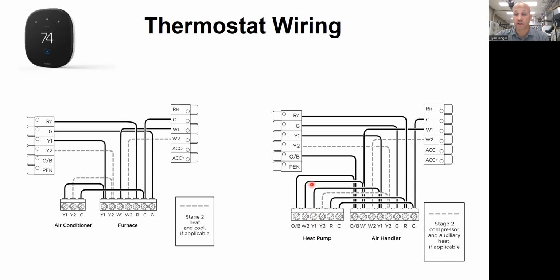the W also. What's going to happen in those cases is W and R at the heat pump will connect to each other. They'll close electrical contact. That'll energize the indoor heater, which can mean electric heater or gas-fired heater, whatever you have. It's going to do that in place of the thermostat. The thermostat can still turn on, let's say it's electric heat, the electric resistance heater when the heat pump can't keep up.